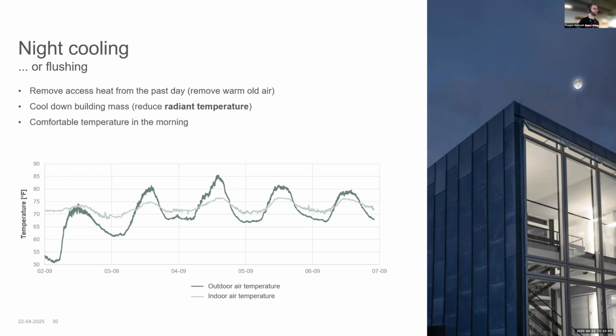I use both terms, cooling and flushing, here because there are really two goals with opening the windows during the nighttime or outside of occupied hours. One is to remove the excess heat from the past day, and the other is to cool down the building mass below the comfort temperature, which reduces the radiant temperature. We talked about the operative temperature a little bit earlier, where it's an average of the radiant temperature and the air temperature. So if we reduce the radiant temperature, we can actually allow a higher air temperature inside the space and still have a good operative temperature.